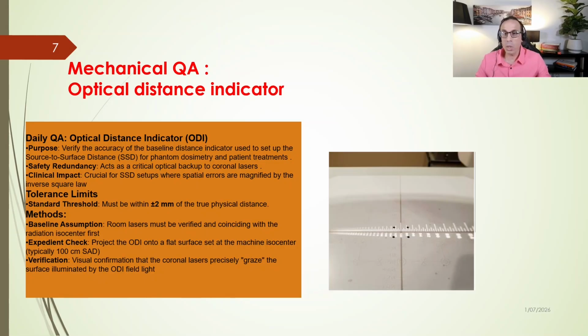It becomes our only reliable setup reference if the patient surface happens to be positioned completely away from the machine isocenter. For example, if you are treating a patient with electron beam at a distance of 110 centimeter, our setup reference will be ODI. So we should make sure that the distance provided by the ODI is correct. Maintaining strict accuracy here is critical, as any physical distance error in an SSD setup technique is heavily magnified by the inverse square law. It means that if we increase the distance from the applicator, our electron output changes significantly and we can underdose the tumor. Because of this clinical impact, our daily tolerance limit is strictly set at plus minus 2 millimeter.